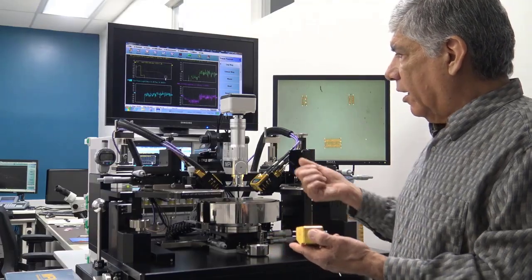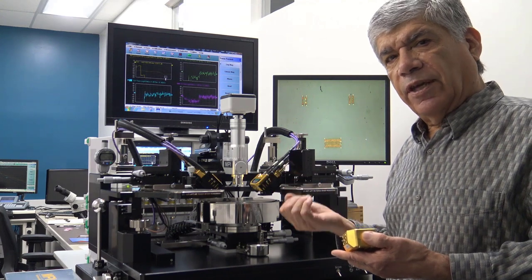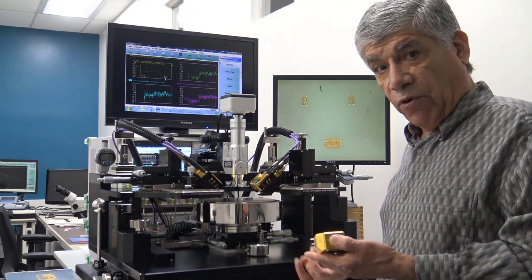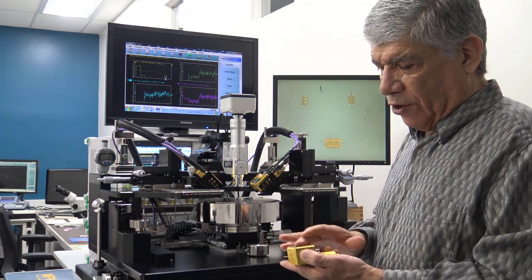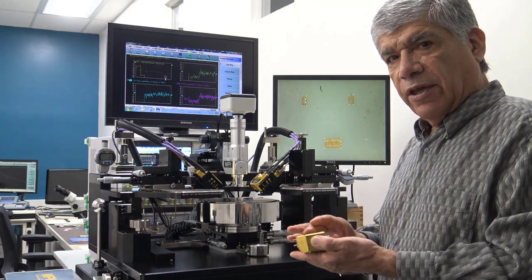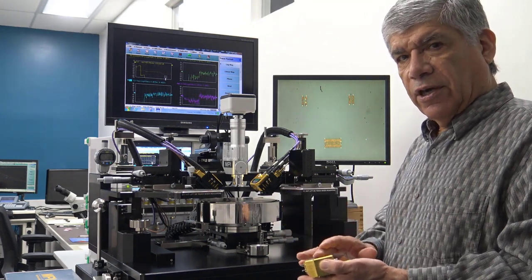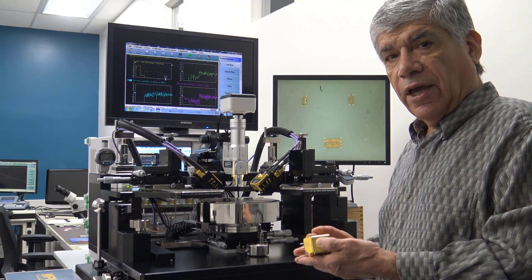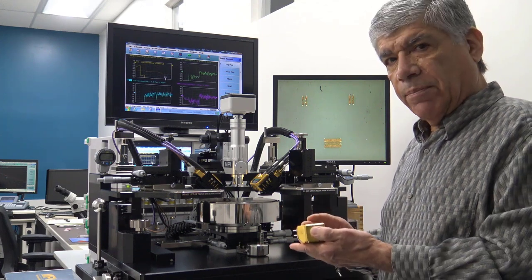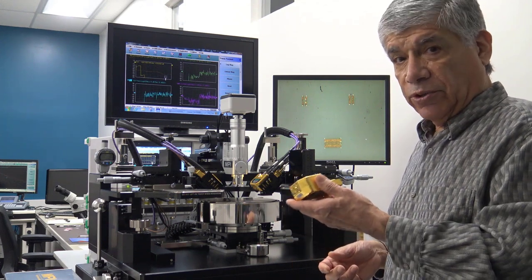The VNA is giving you the baseband frequency from 70 kilohertz up to 54 gigahertz. And then internally we have the sources that go from 54 gigahertz up to 220 gigahertz. And the upper end frequency is dependent on the model of module that you use.